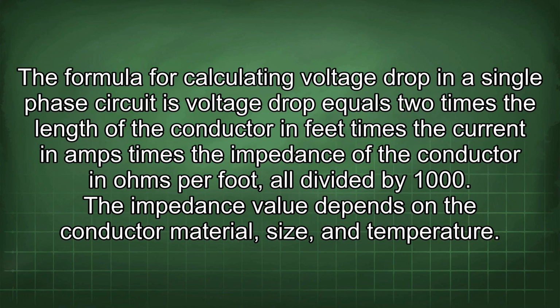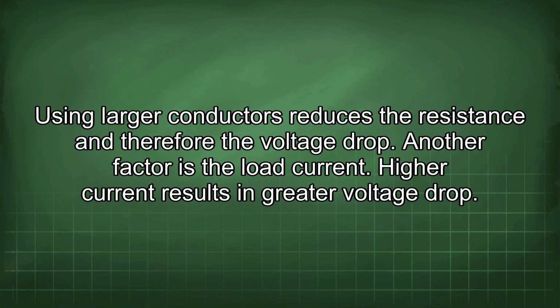The formula for calculating voltage drop in a single-phase circuit is voltage drop equals 2 times the length of the conductor in feet times the current in amps times the impedance of the conductor in ohms per foot, all divided by 1000. The impedance value depends on the conductor material, size, and temperature. Using larger conductors reduces the resistance and therefore the voltage drop.